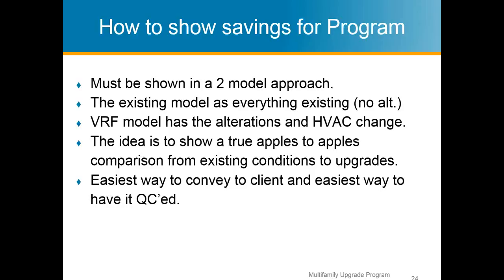And I think after you mess around with working with the VRF modeling approach, you'll understand why. An easy way to understand why is that if you did the alterations tab in EnergyPro and changed out your HVAC, it does it universally, right? Well, you're not going to have one big condensing unit for one individual indoor unit, one residential apartment. You're going to have a larger condensing unit with smaller indoor units, and so, in that logic, it makes complete sense.